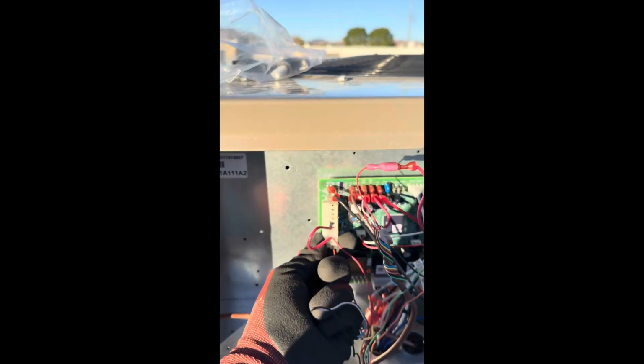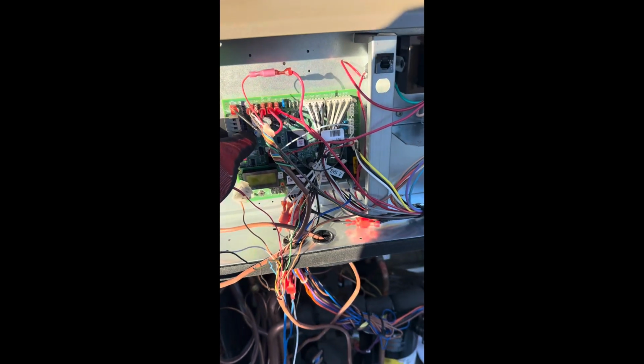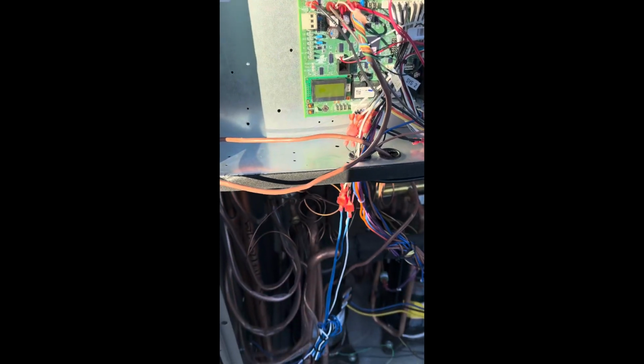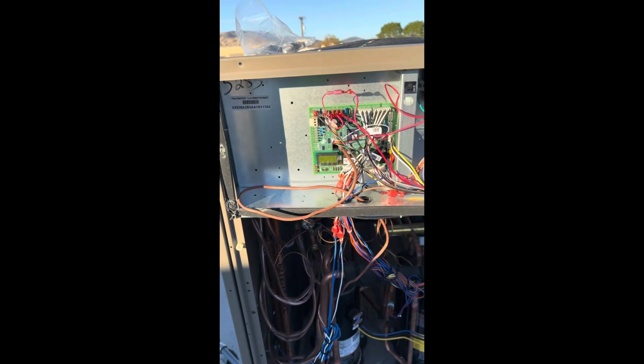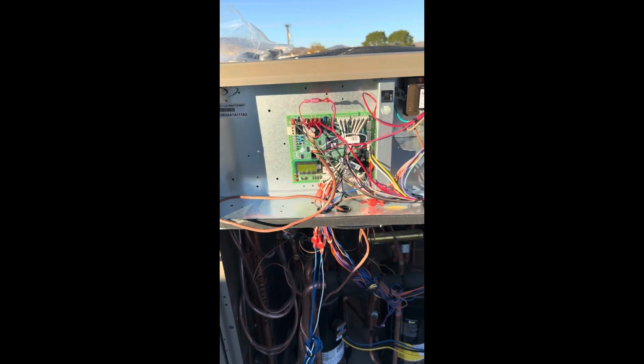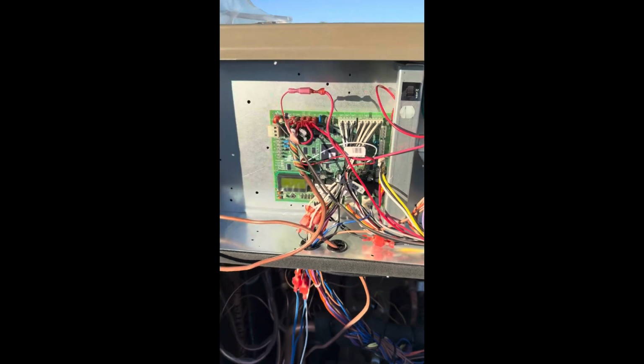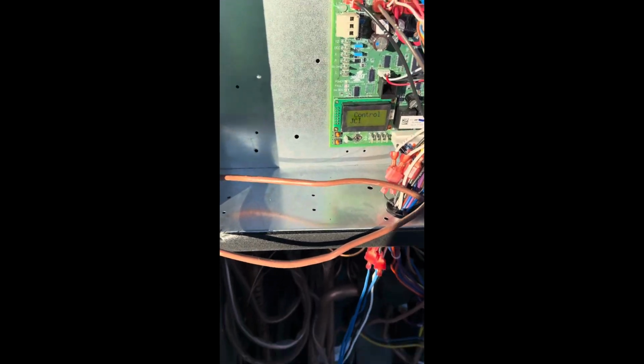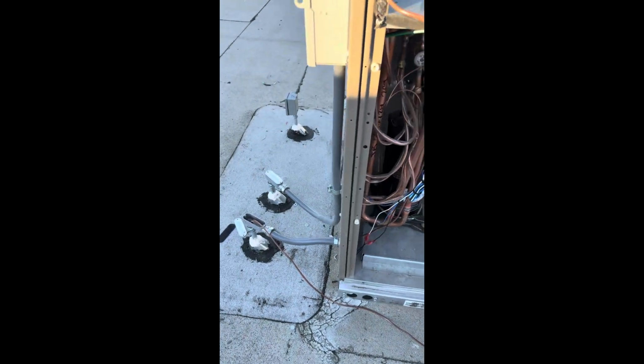Okay, so now what we're gonna do is let's just take this terminal block out. Okay, shut off the power. We're also going to reset our transformer, and then we're going to power it up back one more time. So let's take this one out too. So now that's completely free and isolated, and right away we did have a transformer pop on the first instance, and right now we are good. So we should see the countdown starting up. There we go. So now we confirmed that the low voltage short is in the wire or somewhere along the line. So we're gonna figure that out.